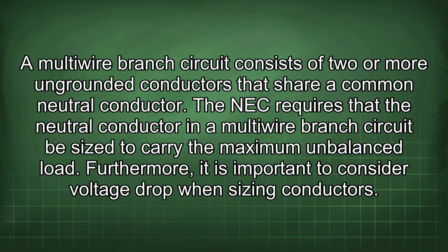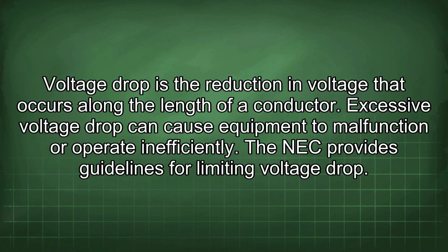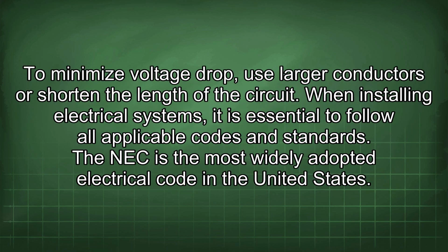Furthermore, it is important to consider voltage drop when sizing conductors. Voltage drop is the reduction in voltage that occurs along the length of a conductor. Excessive voltage drop can cause equipment to malfunction or operate inefficiently. The NEC provides guidelines for limiting voltage drop. To minimize voltage drop, use larger conductors or shorten the length of the circuit.